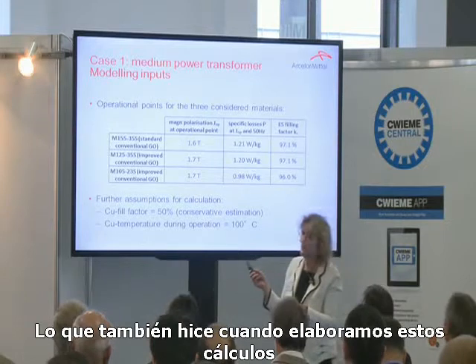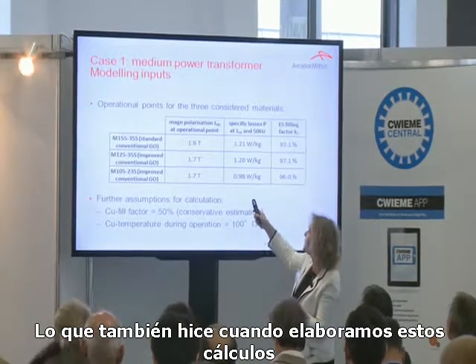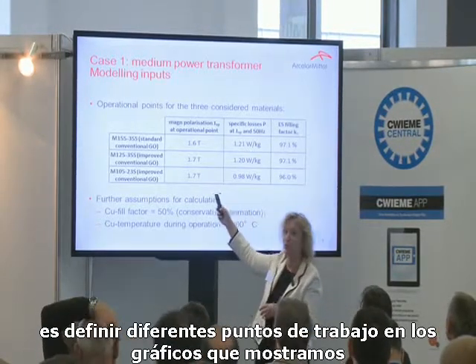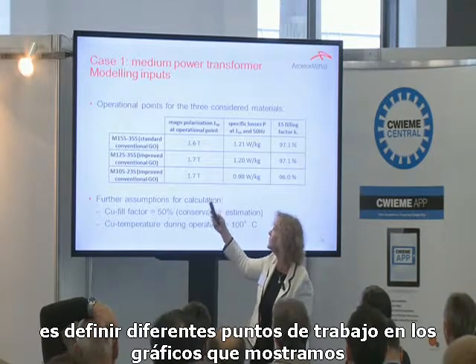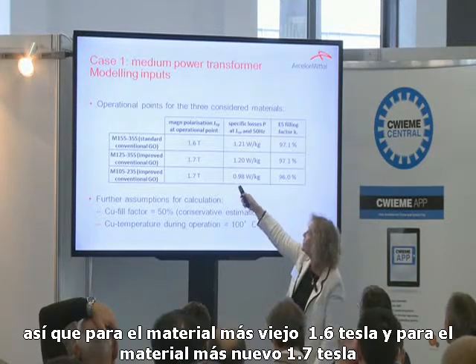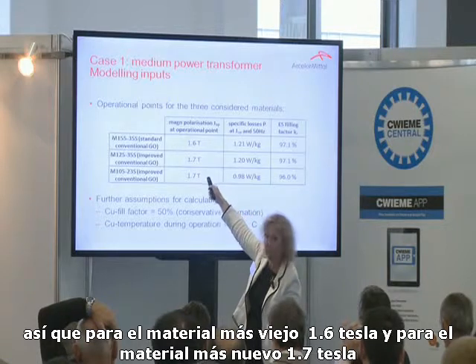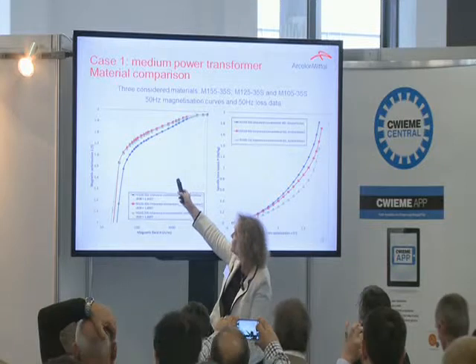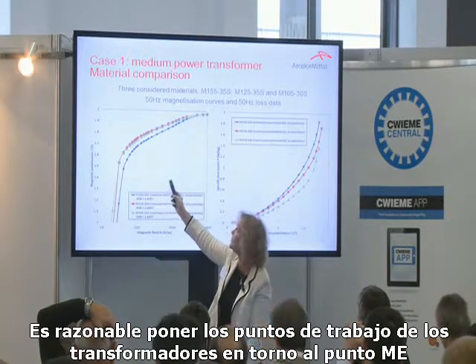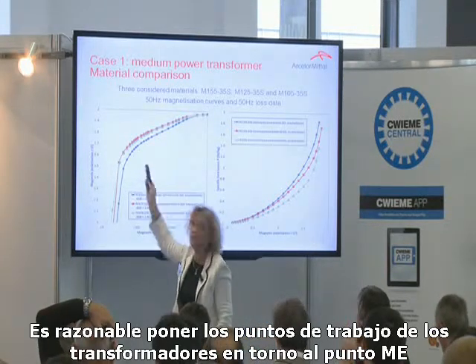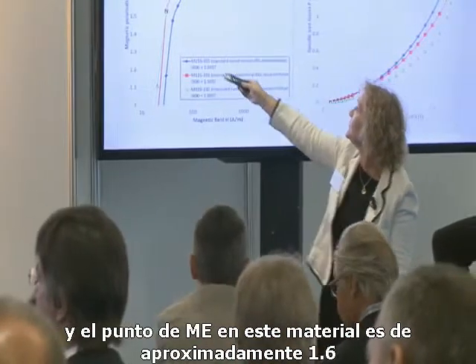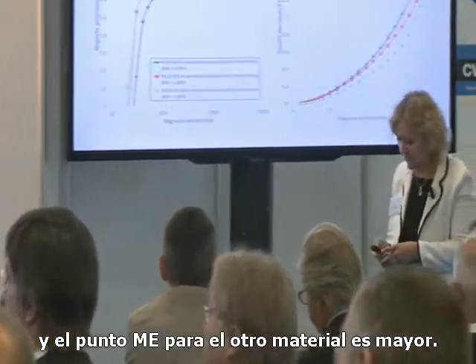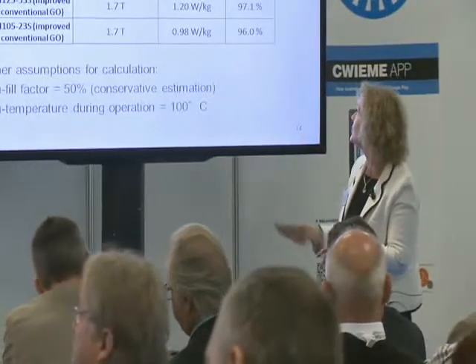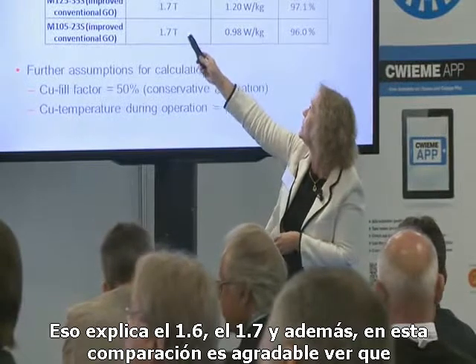What I also did when we did these calculations is we defined the different working points depending on the graphs that we just showed. So for the older material, 1.6 Tesla, and for the newer materials, 1.7. I'll just come back to this graph. It's reasonable to put your transformer's working point at about the knee point, and so the knee point for this material is about 1.6, and the knee point of the other materials is higher. So that explains the 1.6, the 1.7.